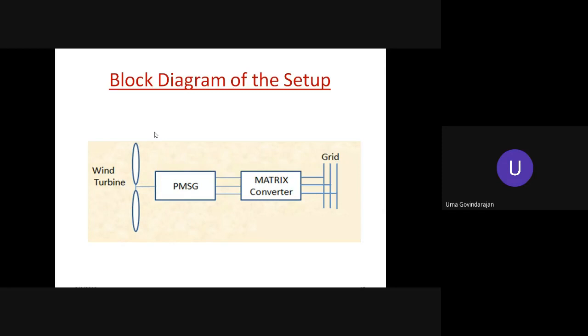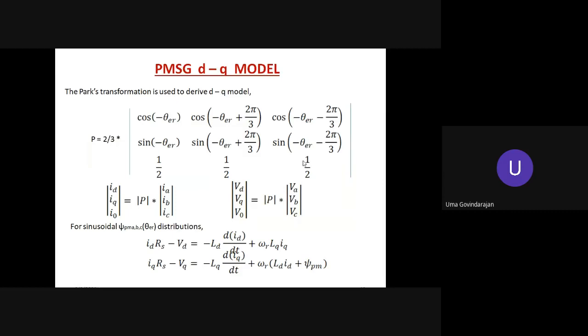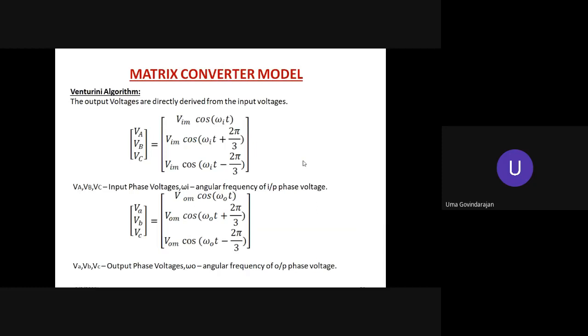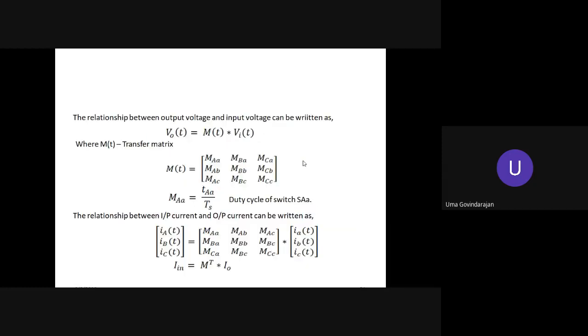This matrix converter matches the variable frequency, variable voltage of the permanent magnet generator to a constant voltage, constant frequency. Assuming a lossless power converter, the active power on the input side is equal to the active power on the output side. This is the mathematical model of the matrix converter. Like an inverter or a voltage source converter, you can control the matrix converter using some pulse width modulation algorithm.